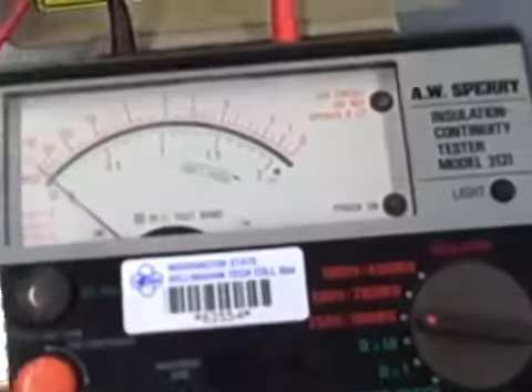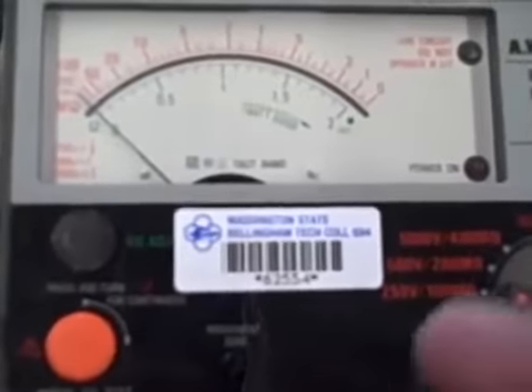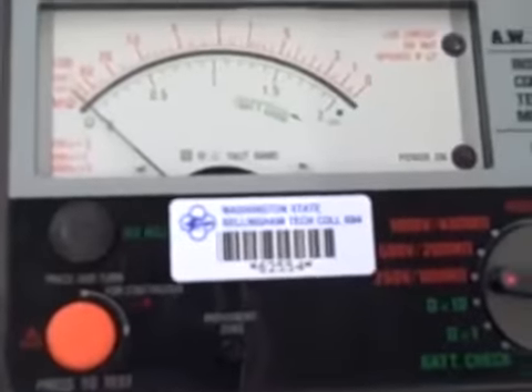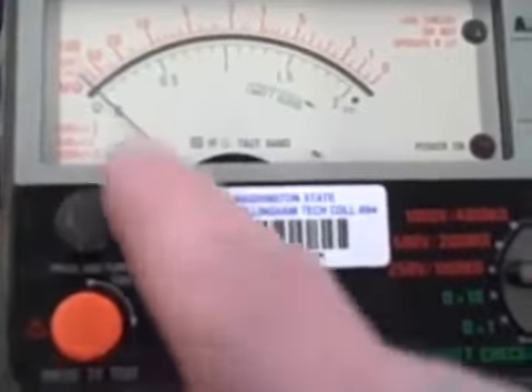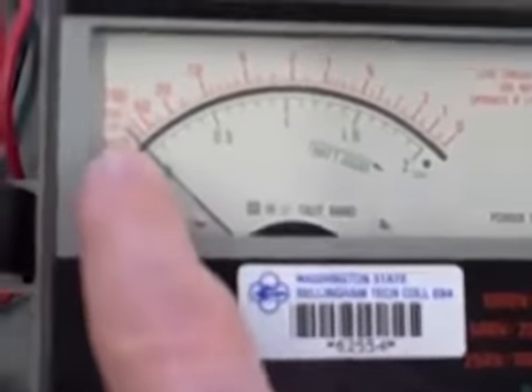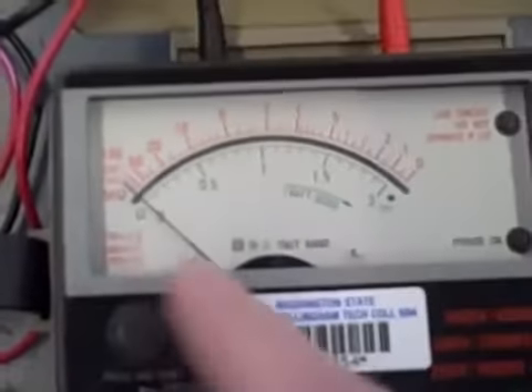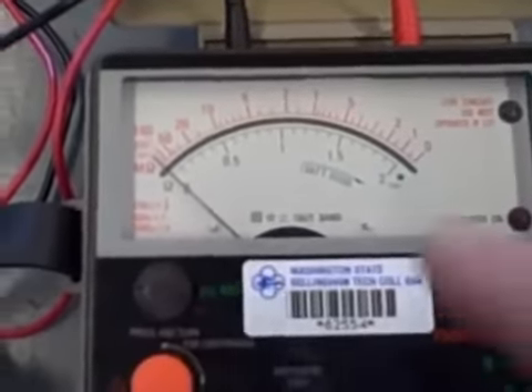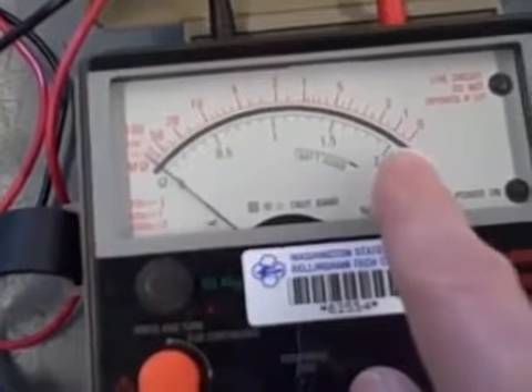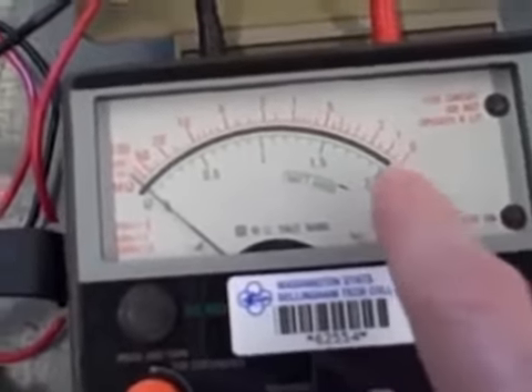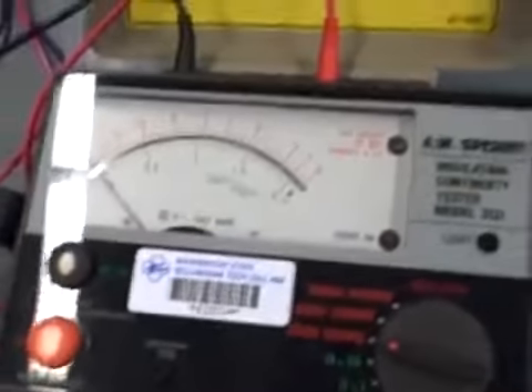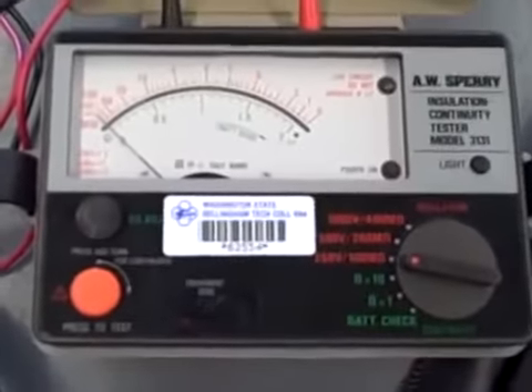Now, if the insulation is in good shape and we don't have any breakdown of the insulation at all, you should measure a very high resistance. The needle should stay on the high megohm end of the scale. On the other hand, if there's a breakdown or a ground fault of the insulation, you'll see the needle swing towards the right-hand side of the scale, possibly all the way to 0 if it's a hard fault to ground. So you need to be aware of this instrument when you use it.